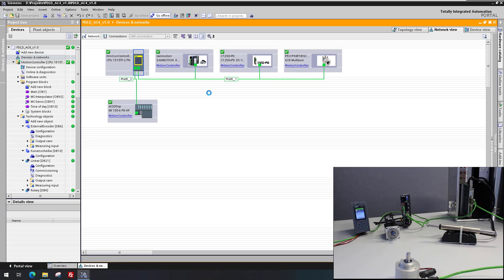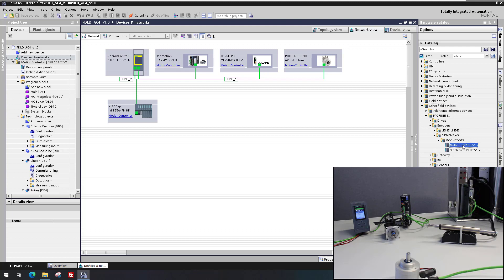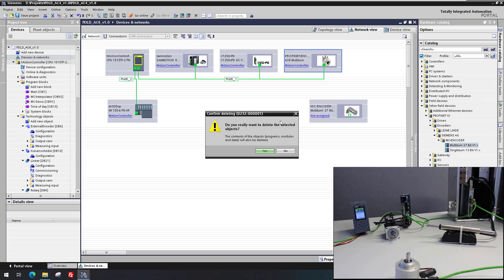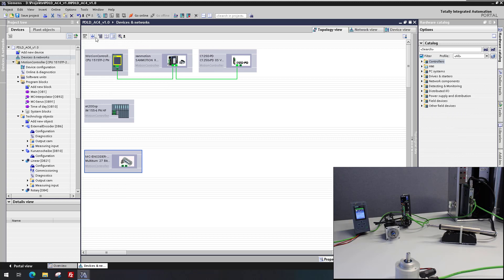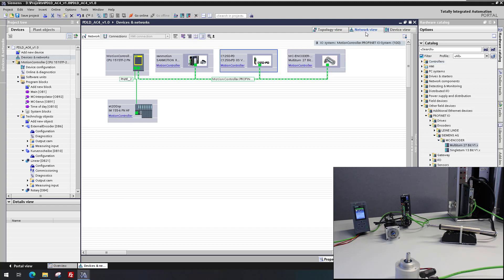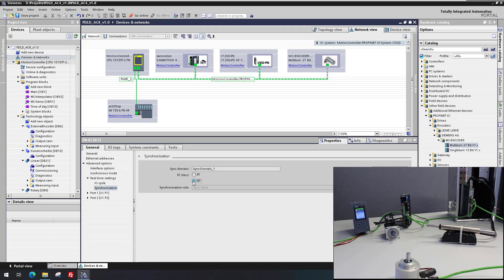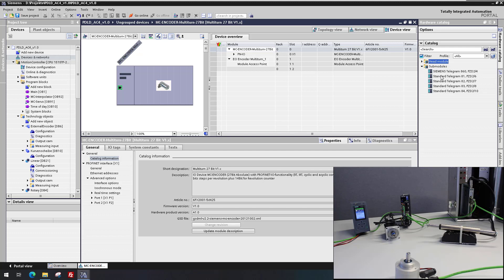Next, the external encoder is exchanged in the configuration. The new device is inserted from the hardware catalog where it was installed via a GSDML file. The previous device can then be deleted. The Profinet connection is set up, and the topology interconnection is configured — mandatory for IRT. The interface is configured for RT class IRT, and the telegram is configured, in this case Telegram 81.